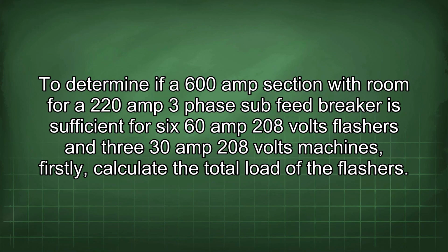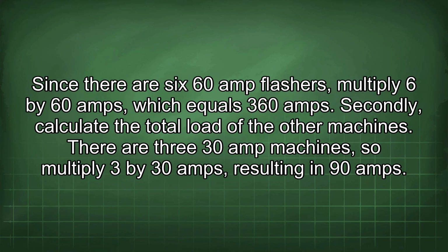To determine if a 600 amp section with room for a 220 amp 3-phase sub-feed breaker is sufficient for 6 60 amp 208 volt flashers and 3 30 amp 208 volt machines, firstly calculate the total load of the flashers. Since there are 6 60 amp flashers, multiply 6 by 60 amps, which equals 360 amps.